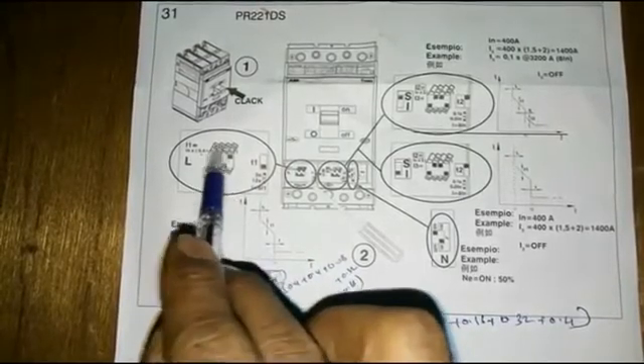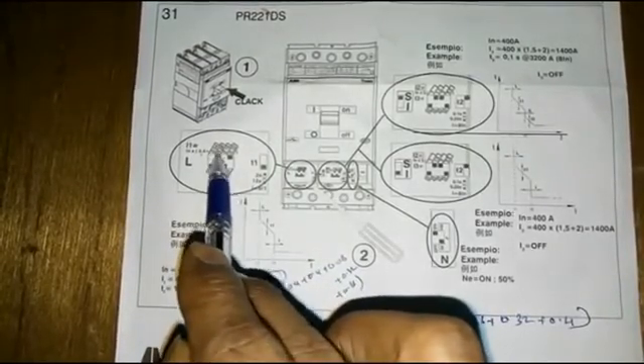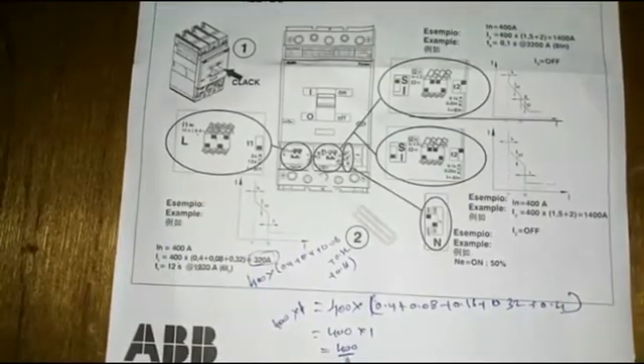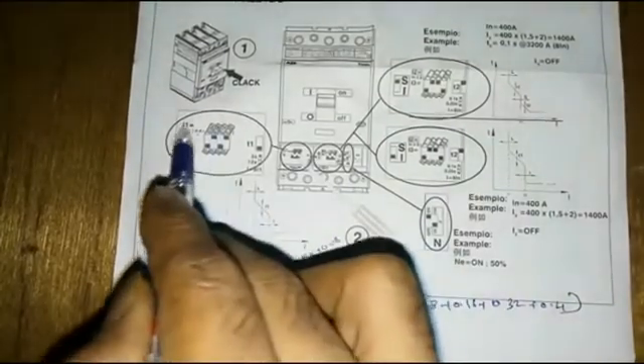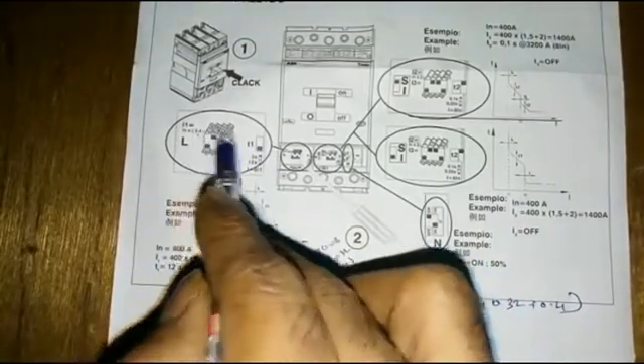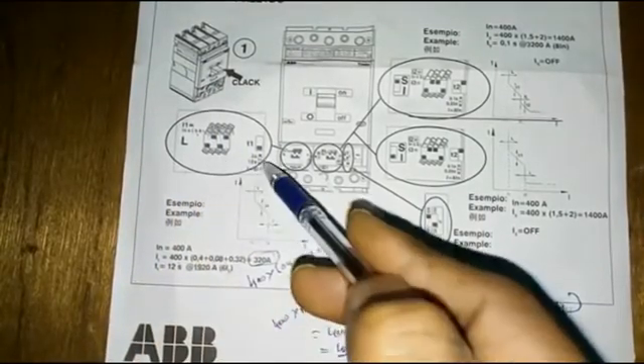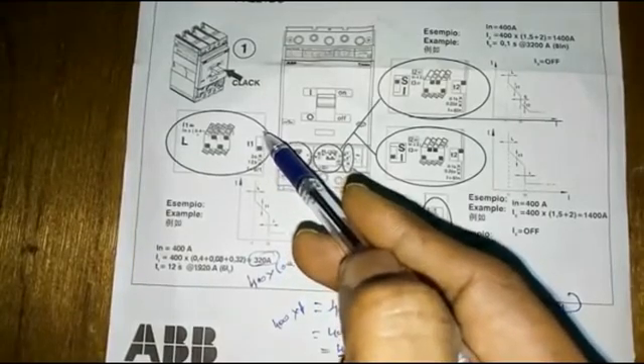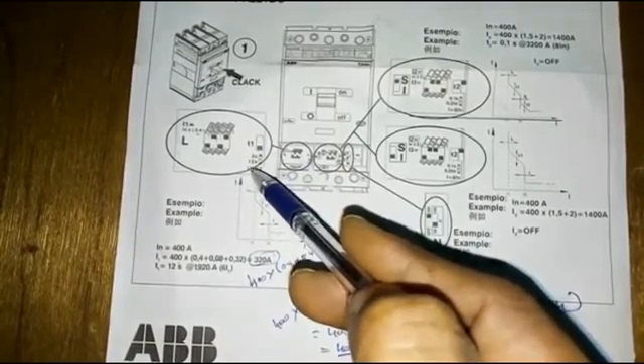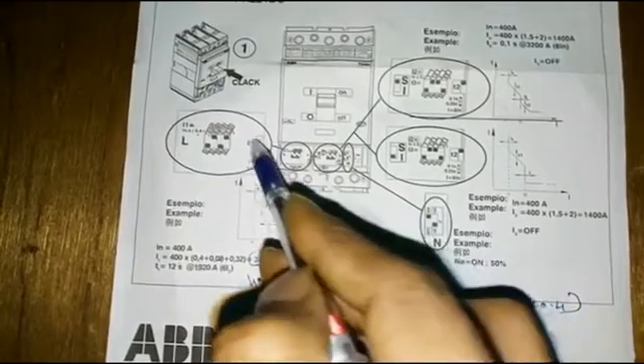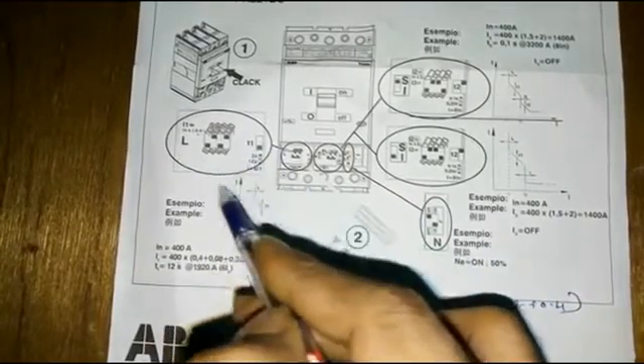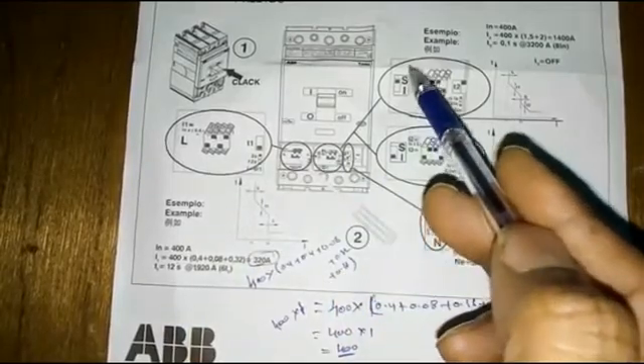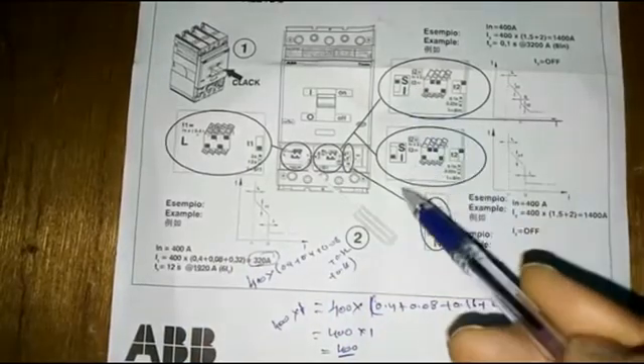When all switches are on top, you are using the MCCB as a full 400 ampere. The timing can also be set: T1 has three seconds and 12 seconds. Switch in top means three seconds; switch in down means 12 seconds. When the current goes beyond 400 ampere, it is going to trip.